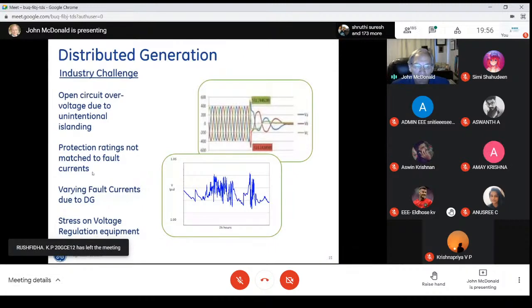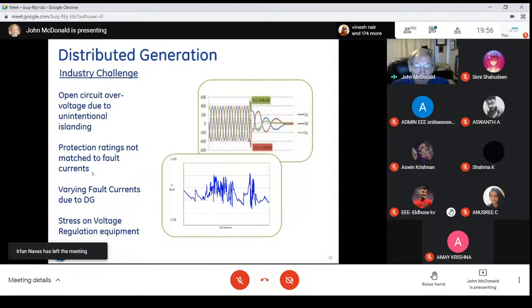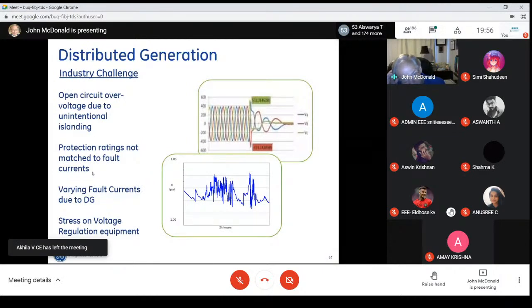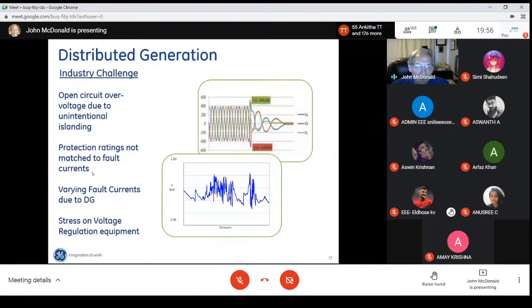When we did a short circuit study, we typically assumed only a source side contribution to the fault. But as the penetration of distributed generation increases, we have a greater contribution to the fault now from the load side. But when we set the relays and did the short circuit study, we typically only looked at the source side contribution and determined the protection ratings that way. That's not accurate anymore, right?